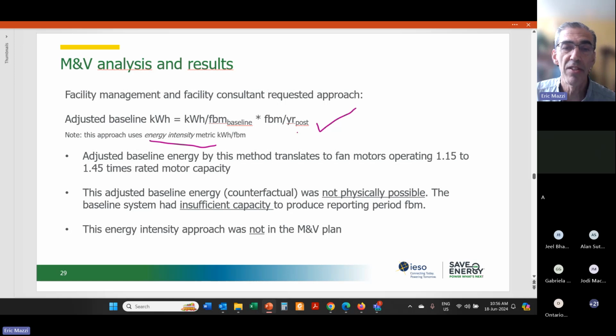The problem was it's physically impossible. Like the baseline system could not produce that number of board feet per year. It could not dry that quantity of board feet per year in the baseline system. The only way it was even theoretically possible is if the baseline fans would have operated anywhere from 15% to 45% above their rated capacity for all operating hours of the year, which of course is impossible. The motors would have burned out. So the proposed, what would be called counterfactual, was just physically not possible. And the baseline system just did not have sufficient capacity.